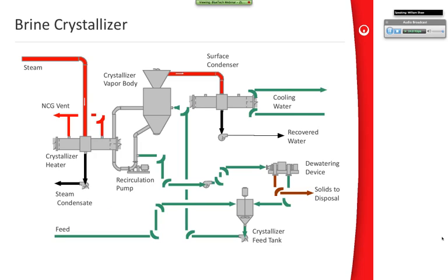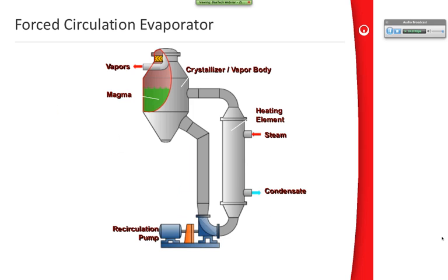The brine crystallizer, we showed that before, is a forced circulation unit. This is a typical steam-driven, single-effect forced circulation brine crystallizer. Here's the forced circulation evaporator. There's a condenser to condense the final vapor. That's our distillate water. There's a solid separation device, which I'll show you a couple different examples of in a minute, either centrifuges or filters. And then there's a tank to collect mother liquor and feed and put that back into the crystallizer. So you can see the only output from the system is the distillate water, which is recovered, which hopefully we can recycle, and solids, which go to either disposal or reuse.